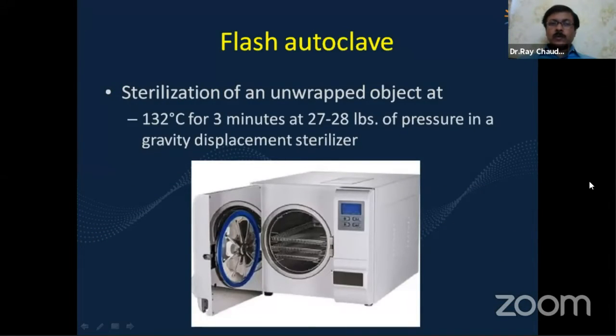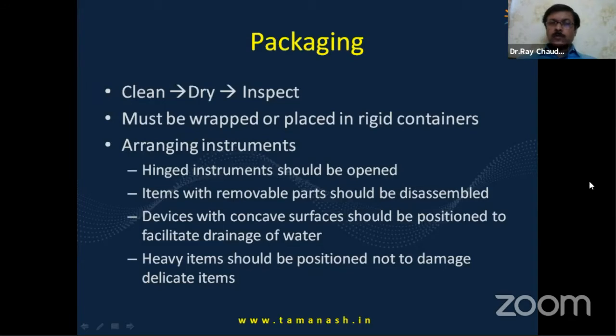Now we have the flash autoclave, which is for sterilization of instruments in between cases, and it works at 132 degrees for 3 minutes at 27 to 30 pounds of pressure. But remember that this is a gravity-dependent sterilizer. There is no pre-vacuum. So if you are using it to sterilize handpieces and tubings in between surgeries, only the outer surface will be properly sterilized. The lumen may not take in steam at adequate pressure and temperature. Also, flash autoclaves are to be used without the instruments being wrapped, directly on the tray.